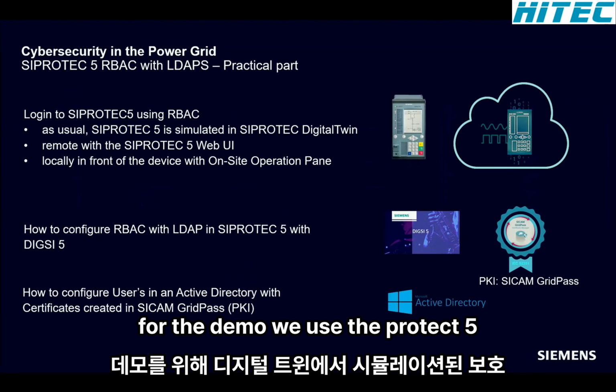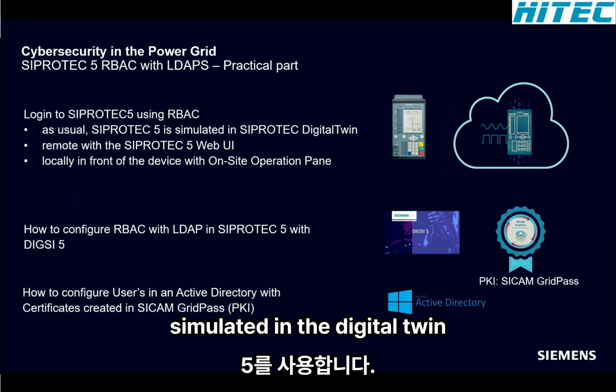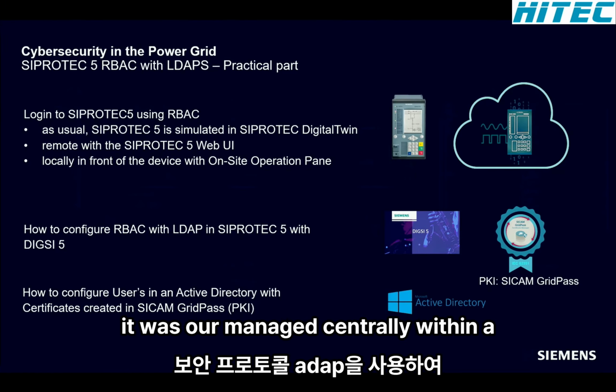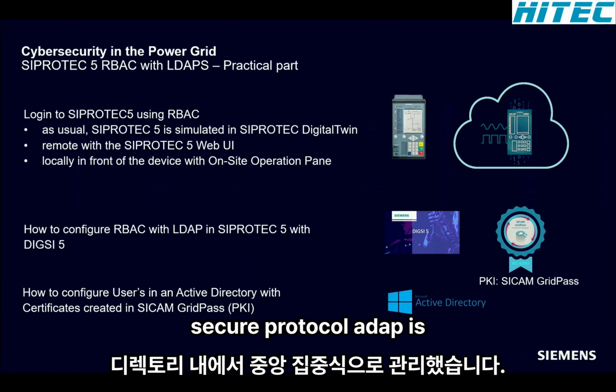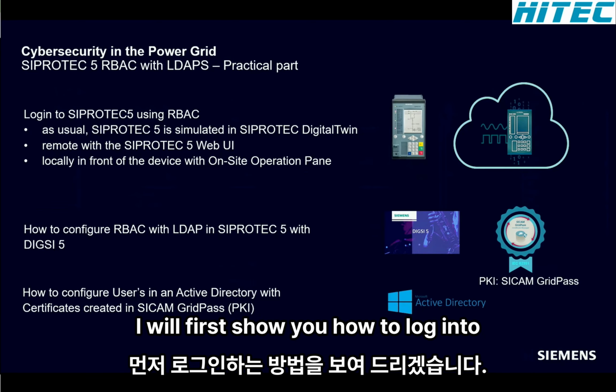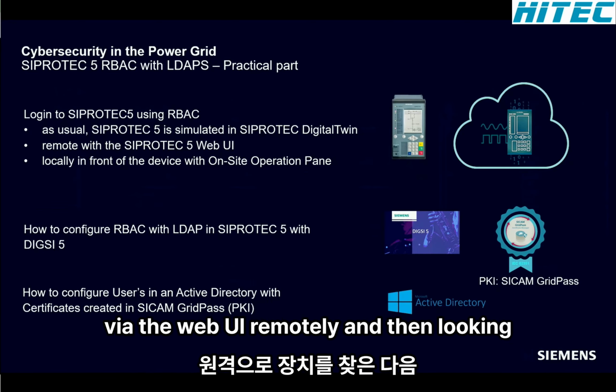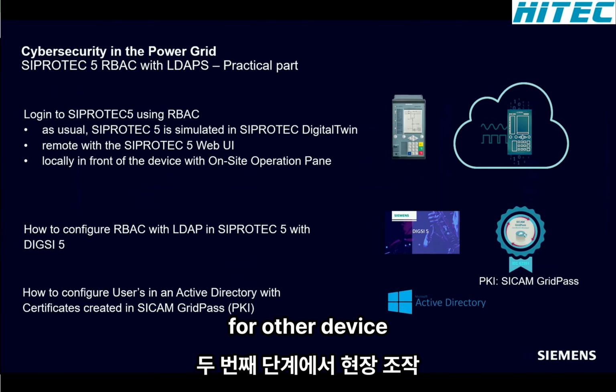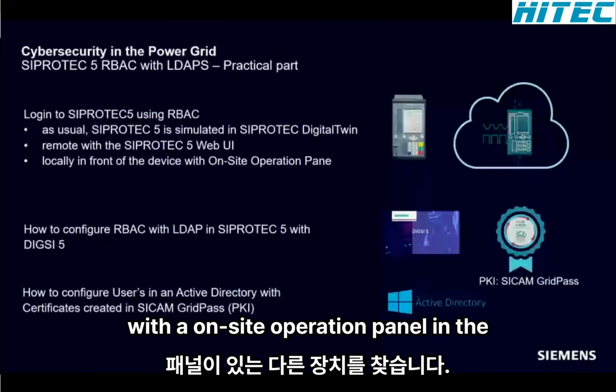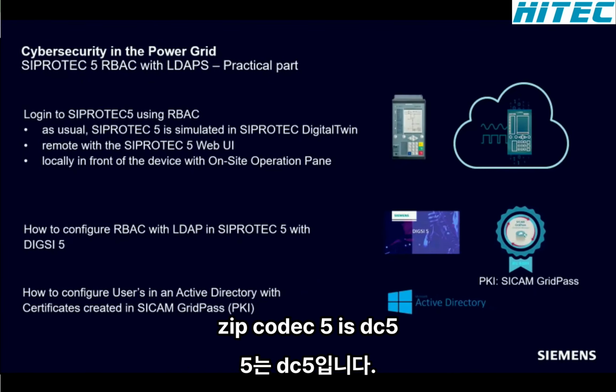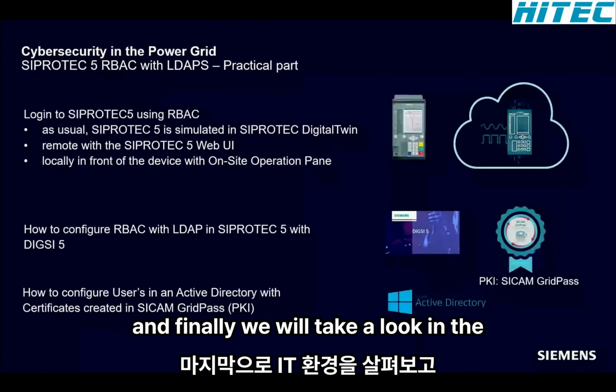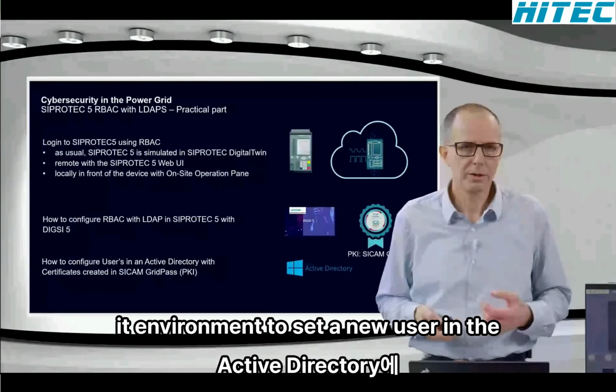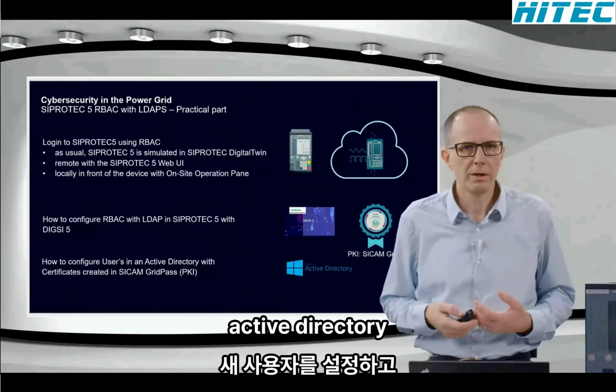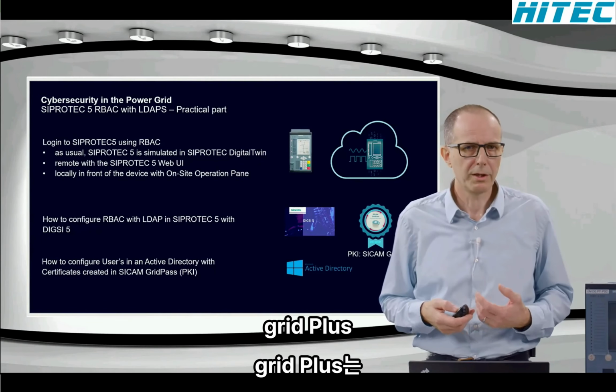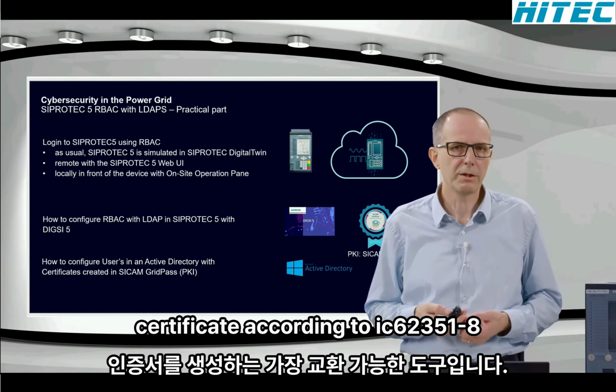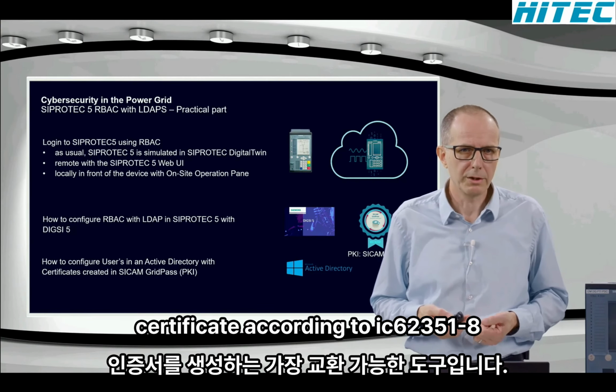For the demo, we use SIPROTEC 5 simulated in the digital twin. Users are managed centrally within a Microsoft Active Directory using the secure protocol LDAP-S. I will first show you how to log into the device via the web UI remotely, and then log in locally with an on-site operation panel. In the second step, I will configure LDAP in SIPROTEC 5 with DIGSI 5. And finally, we will take a look in the IT environment to set up a new user in the Active Directory and create the user certificate with SICAM GridPass, the most convenient tool to create certificates according to IEC 62351-8.